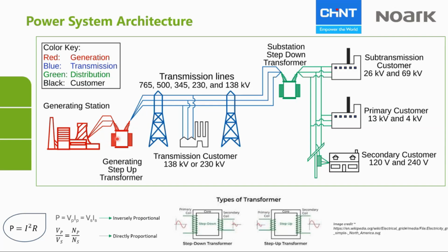Now, when the power that you are getting from the generating station gets to the transformer, the part that it gets to first is the primary. And when it leaves the transformer, that side is known as the secondary. But as you can see here, what the transformer does is it transfers energy from one circuit to another one. So the power remains the same. For example, if the generating station is generating 2000 megawatt, it's that same amount of power that is going to leave the transformer.